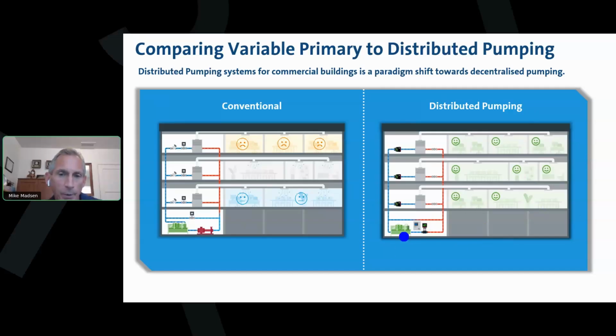So we still have a primary pump. We've got our chiller. Like primary secondary, we have a decoupler. We have 3 air handlers, but now instead of these control valves that waste a lot of head pressure, we have one of the smart pumps and a check valve. And the reason for the check valve is, if this middle air handler is not running, we don't want to short circuit any chilled water through the air handler. You see all the smiley faces. This is a self-balancing system. So if you're a balancing contractor on the call, your balancing job is going to be a lot simpler. If you're doing a new installation, the balancing cost is going to be a lot lower because it's self-balancing.